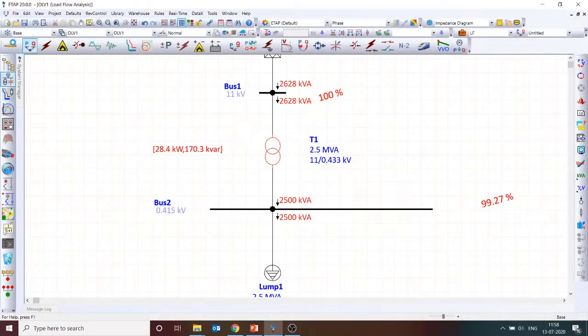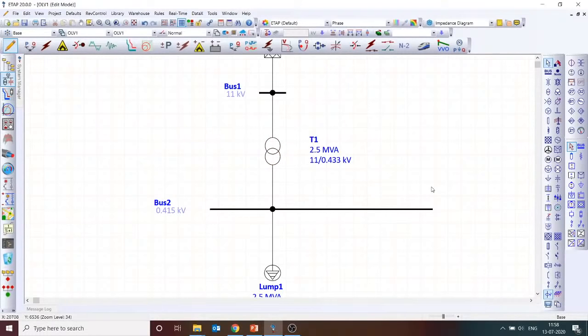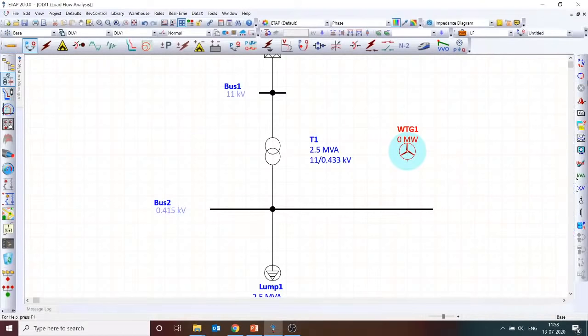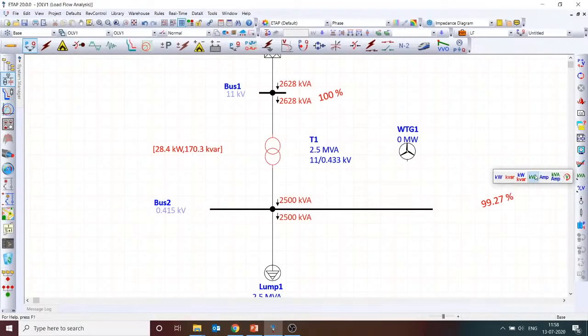Fine. Now let's add a solar inverter or a wind turbine generator. For easiness, let me add a wind turbine generator. I will take up the solar inverter tomorrow. Before adding the wind turbine generator, let me look at the power factor also. That's another important aspect which you need to look into. So let me go back to kilowatt and kVAr: 2000 kilowatt, 1500 kVAr, that is 0.8 power factor.